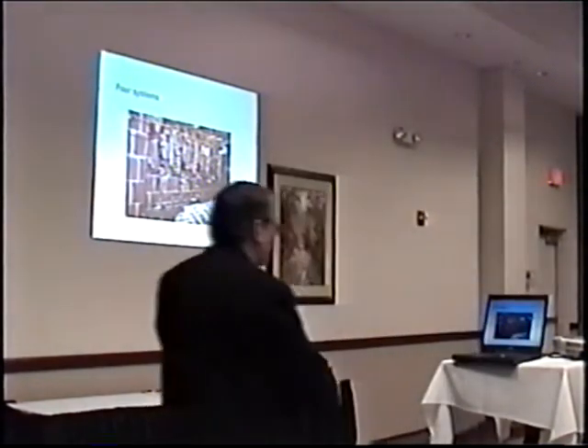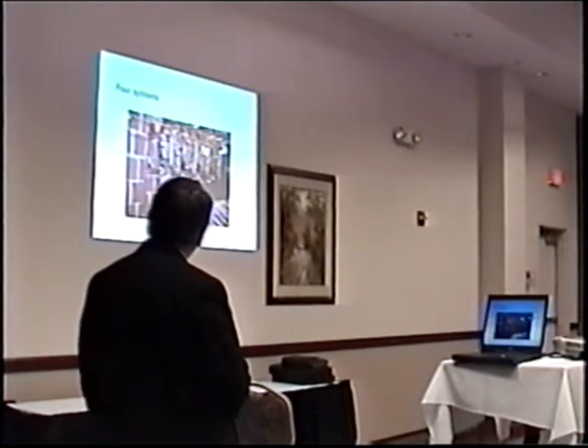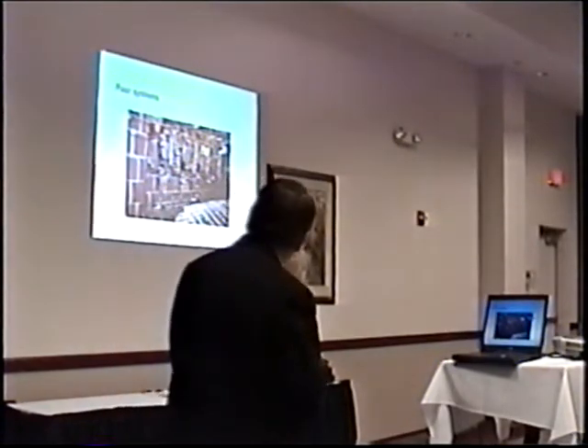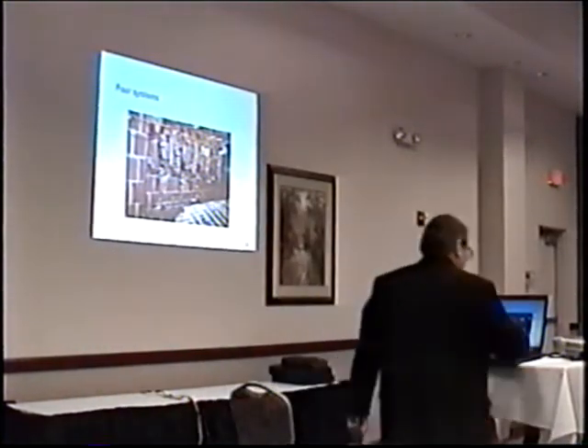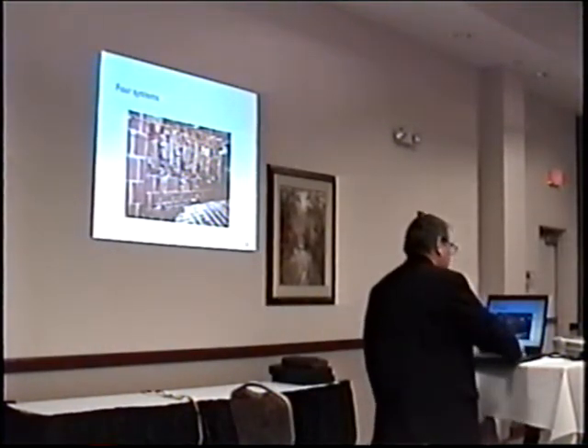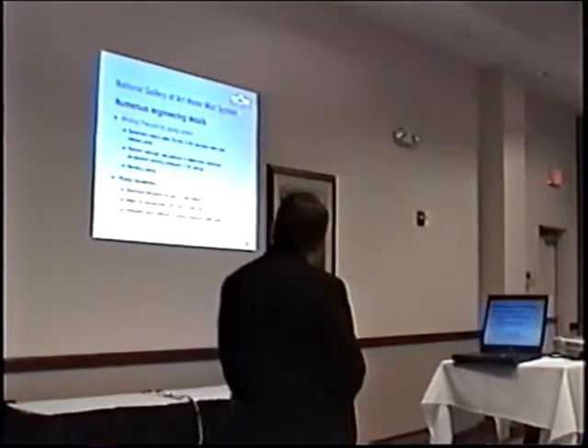For the 10 additional galleries, I've got actually 6 systems. There's 4 of them here protecting the bulk of the galleries. And it's all kind of modeled after piping systems I've seen in Alaska. I won't get into the details of all that. This consists of 4 27 kilowatt motors as pumping assembly. The building was equipped with 220, and we had to put in a transformer to get to 480.